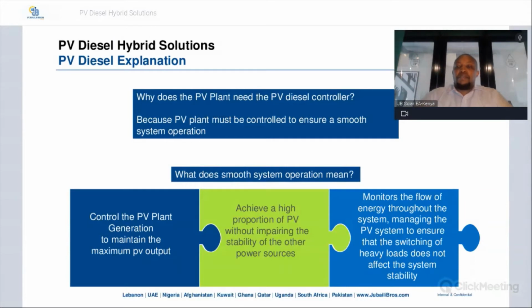So why does a PV plant need the PV diesel controller? We need to make sure that the overall system works in a smooth and efficient way. So this is achieved by controlling the PV plant, making sure that you're generating and maintaining the maximum PV output. You want to achieve a high proportion of PV without impairing the stability of other power sources. And other power sources in this case could be the diesel generator, battery storage systems, or the grid.